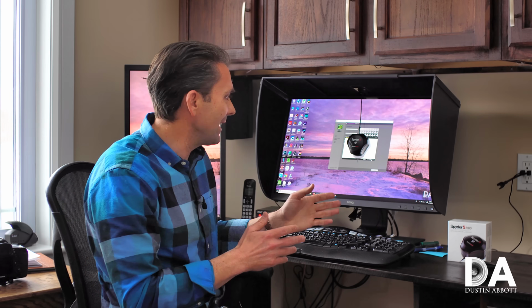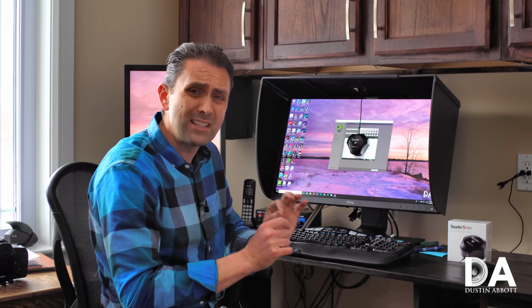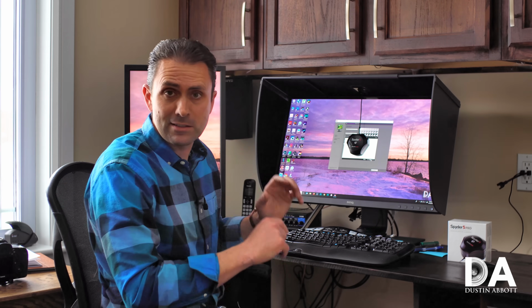But of course, there are factors that come into play when it comes to calibration. For one thing, the environment in which you use the monitor, and so your ambient light can be a factor. Another factor is that the behavior of monitors long term is not always permanent. There can be some variation, and in fact, after using the monitor for several weeks, I started to get a notice when it's powering up at the beginning: your monitor needs to be calibrated. Not because it wasn't calibrated to begin with, but just as a reminder that calibration can subtly shift over time. And so doing periodic calibration certainly is a wise thing, just to make sure that you're getting optimal performance out of your expensive, and in this case, fantastic monitor.